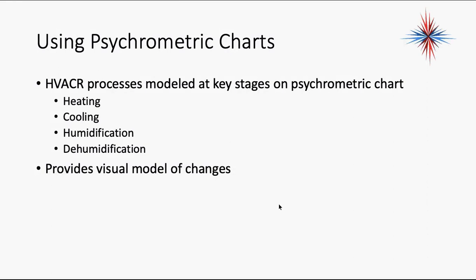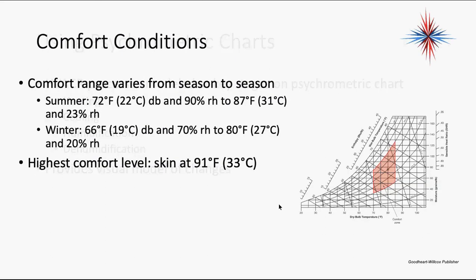HVAC processes are modeled at key stages on this chart. You have a heating process, you have a cooling process, you have a humidification process, and you have a dehumidification. All we're doing here is, remember, yesterday I put a cooling process up there. I said, here's my return air, here's my supply air. What is the process? What are we having to do with that air to get to those points? It provides a visual model of the change.